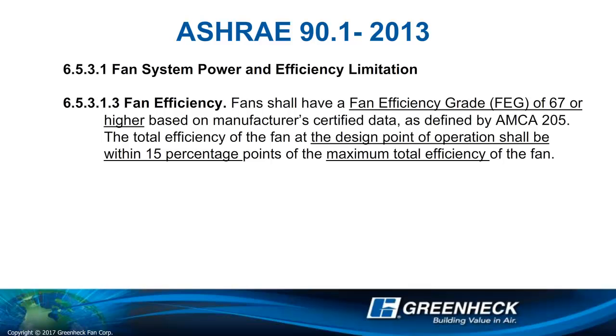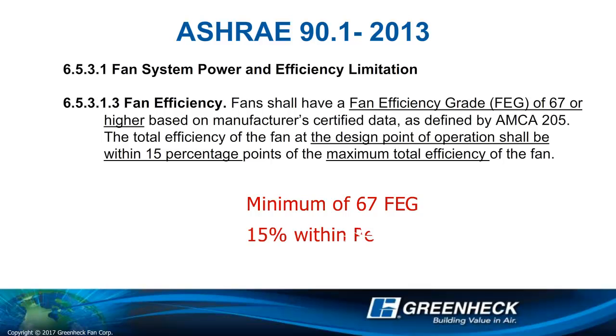We will focus on Section 6.5.3.1, Fan System Power and Efficiency Limitation. It states that fans shall have a fan efficiency grade, also known as FEG, of 67 or higher. This is based on the manufacturer's certified data as defined by AMCA 205. Also, the total efficiency of the fan at the design point of operation shall be within 15 percentage points of the maximum total efficiency of the fan. In other words, a minimum of 67 FEG and the fan's operating point needs to be within 15 percentage points of peak total efficiency.